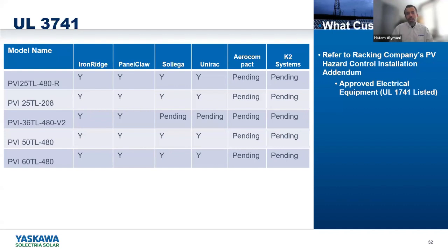piece of the puzzle is: are we certified to utilize 3741? The certification actually does not involve the inverter manufacturer, and we're not the party that needs to get this certification. The party that needs to get the certification is actually the racking manufacturer. So on the racking manufacturer's installation manual, if you go to the hazardous material addendum at the end of the installation manual, you will see a list of all the inverter manufacturers that are UL 3741 listed with this racking manufacturer.